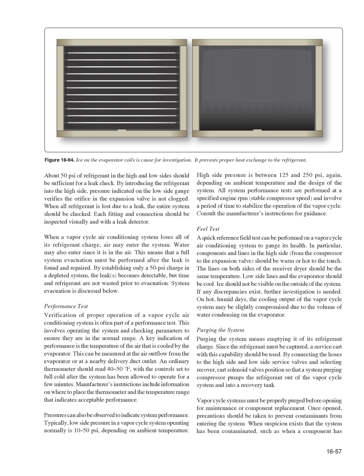Purging the system. Purging the system means emptying it of its refrigerant charge. Since the refrigerant must be captured, a service cart with this capability should be used. By connecting the hoses to the high side and low side service valves and selecting recover, cart solenoid valves position so that a system purging compressor pumps the refrigerant out of the vapor cycle system and into a recovery tank. Vapor cycle systems must be properly purged before opening for maintenance or component replacement. Once opened, precautions should be taken to prevent contaminants from entering the system.